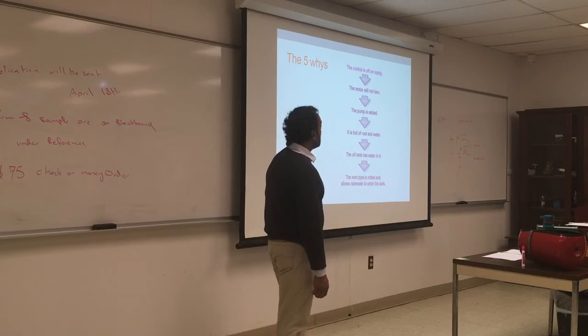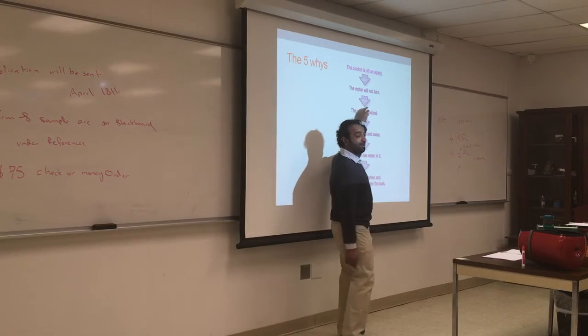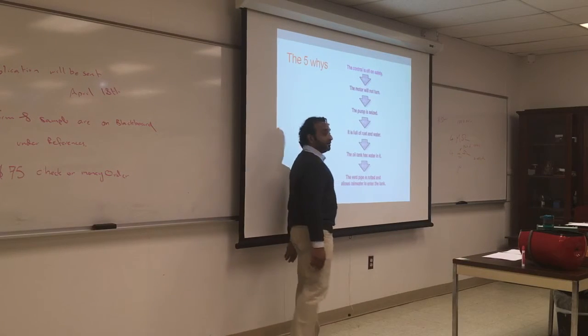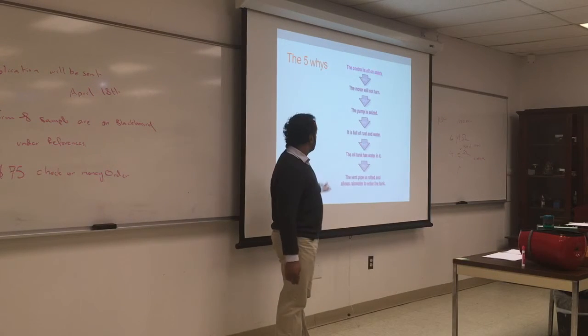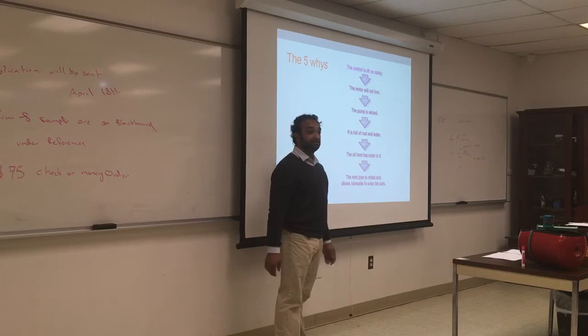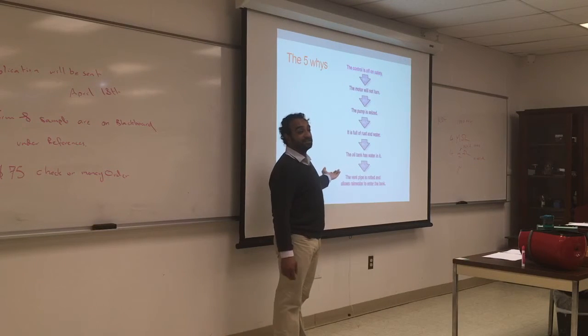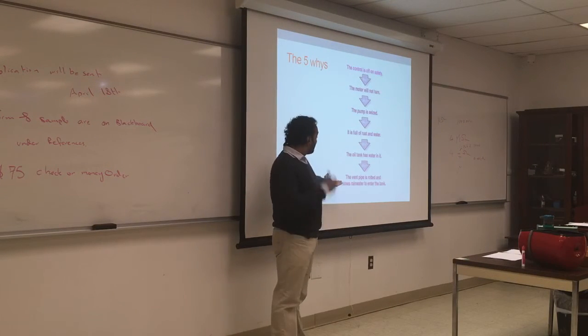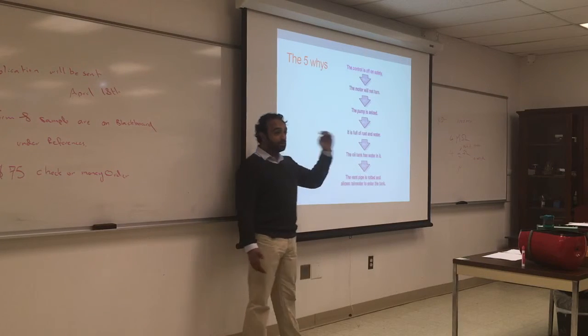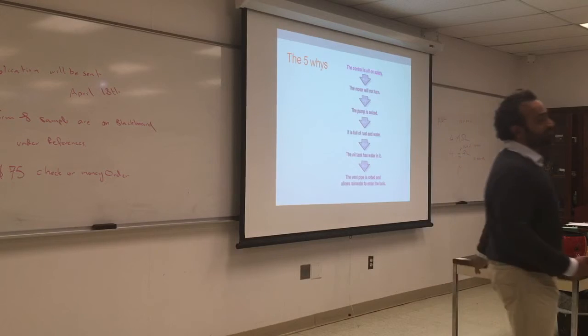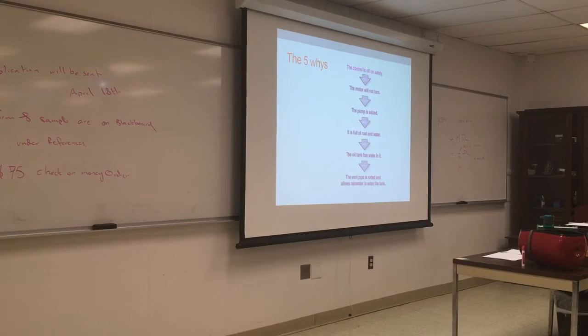Again, why? Because at any stage you will fix the problem, it will come back if you don't get the root cause. Rust and water, why does it have rust and water? The oil tank has water in it. Okay, the oil is not supposed to have water in it. There's a solution. Yeah, so the vent pipe is closed. So you're always going to go to this root cause analysis and try to find what actually caused the problem. Otherwise, you'll fix it and it will come back again.